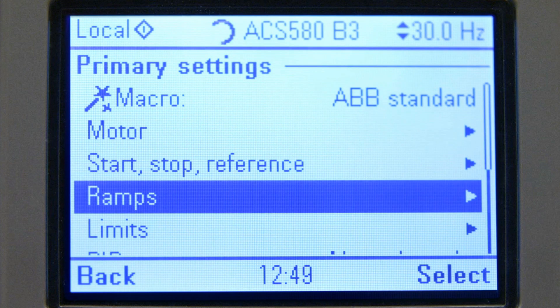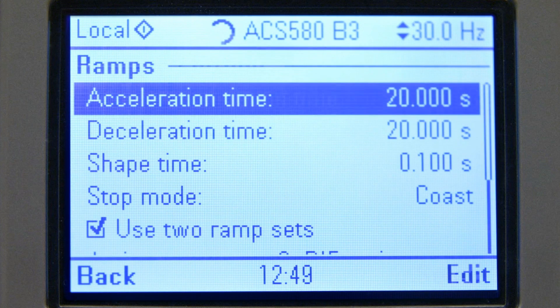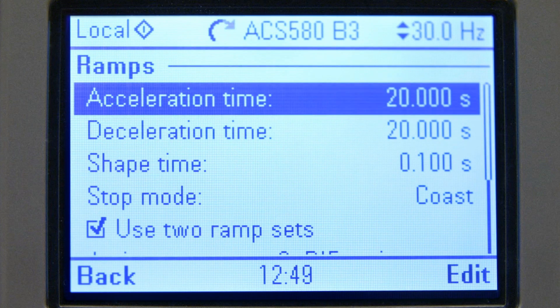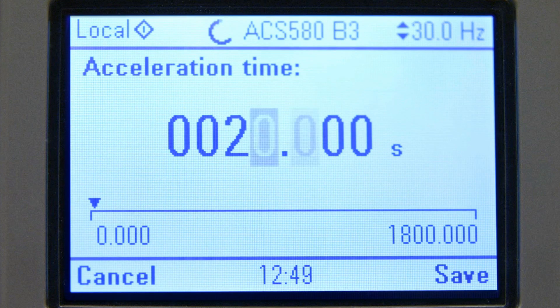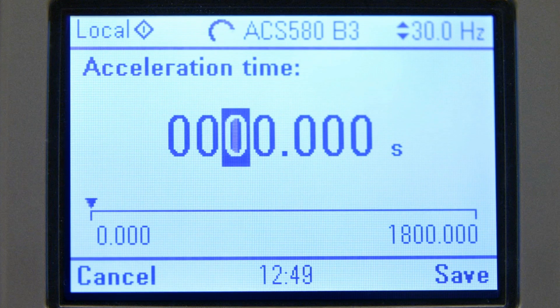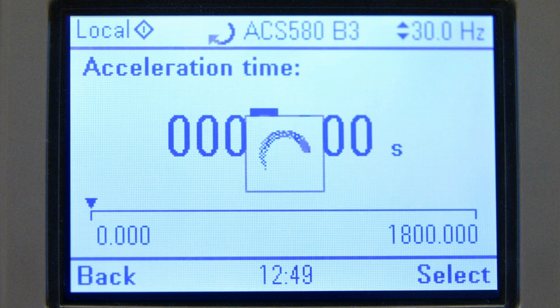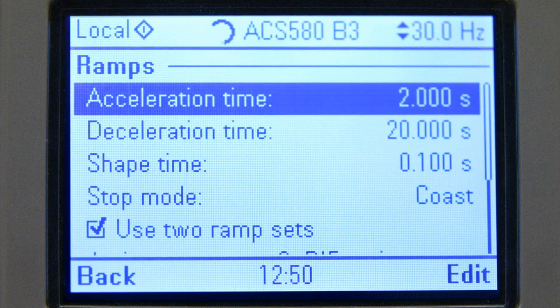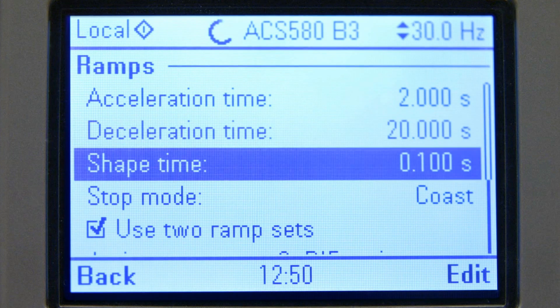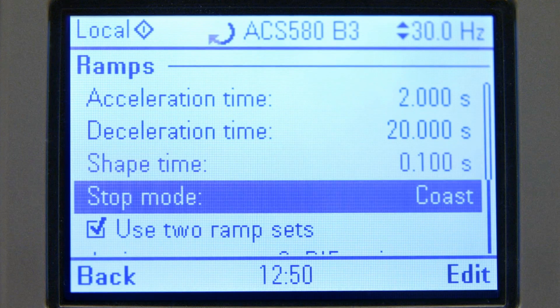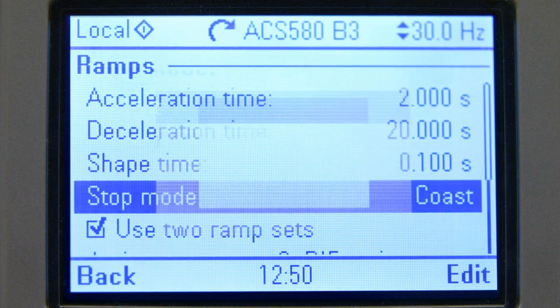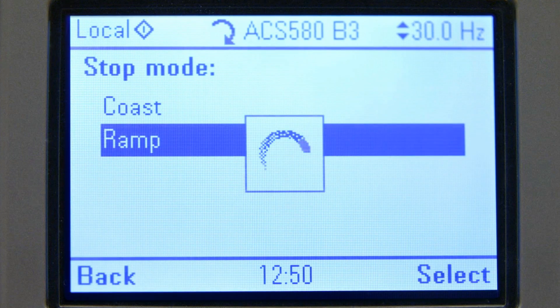Typically, we need to adjust the ramp times in every application. Here we need a short ramp time, so we will set the time to 2 seconds for start and stop. Stop mode has to be changed to ramp stop to use the deceleration ramp.